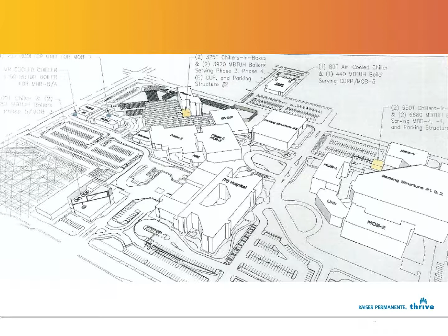You've got 6 air changes per hour in your LDRP rooms, 6 in patient rooms, 6 in exam rooms, 6 in x-ray rooms and diagnostic areas, 4 in hallways. That's what's killing the energy signature. I tell HVAC guys in presentations: forget about the ORs, it's a red herring. Sure, you can save energy in an individual OR with turn-downs and temperature resets, but you'll never see that on the bills. If you want a measurable impact on the energy bills at this campus, you've got to go after the most common spaces: patient rooms, hallways, the D&T exam rooms, bathrooms. That's where the energy's at.